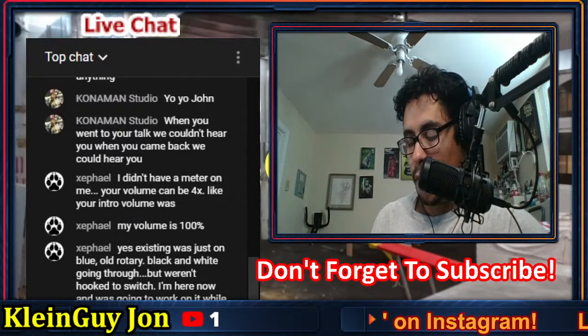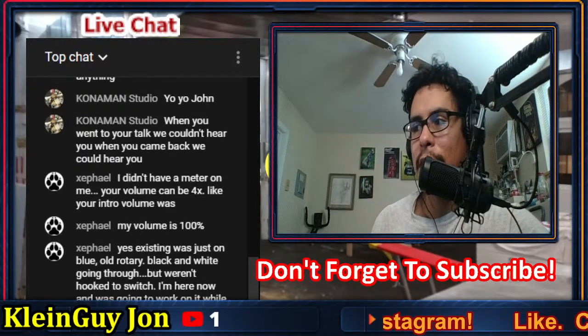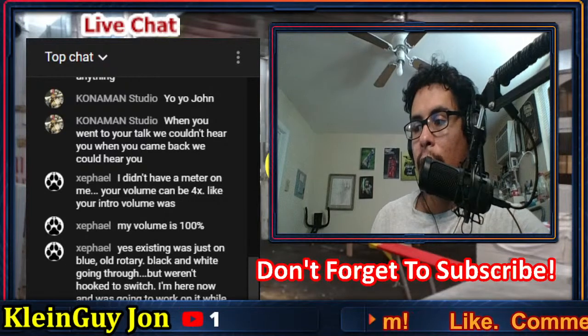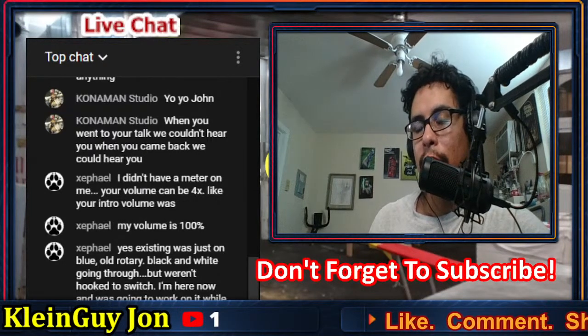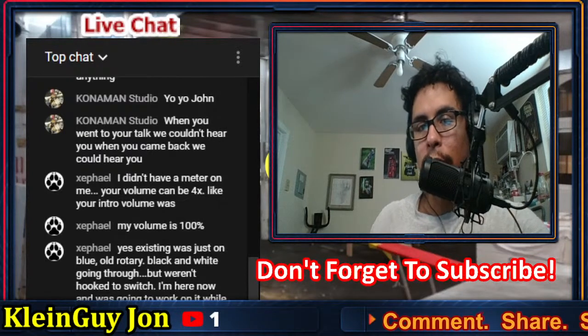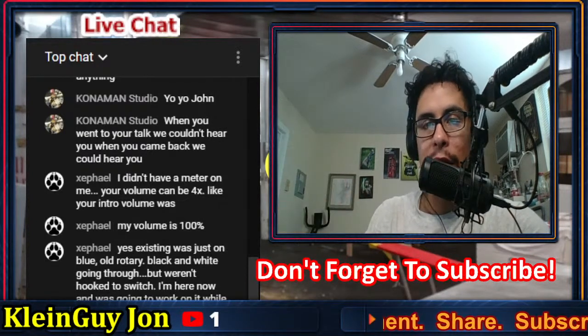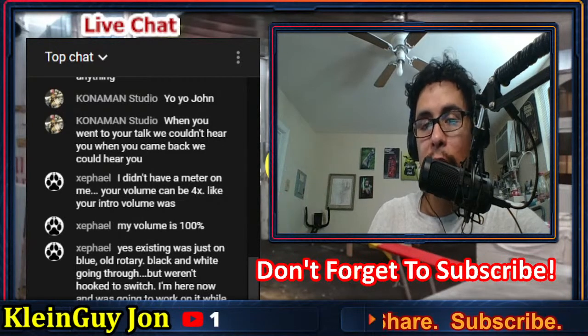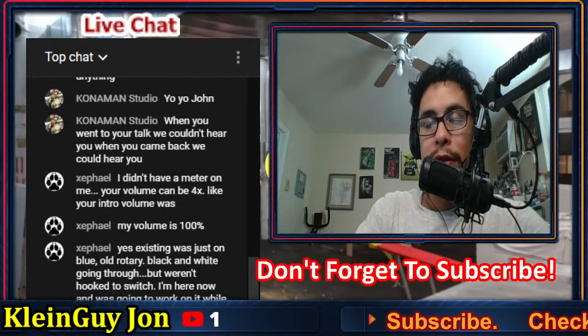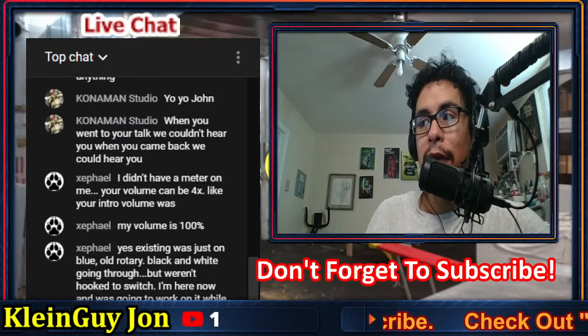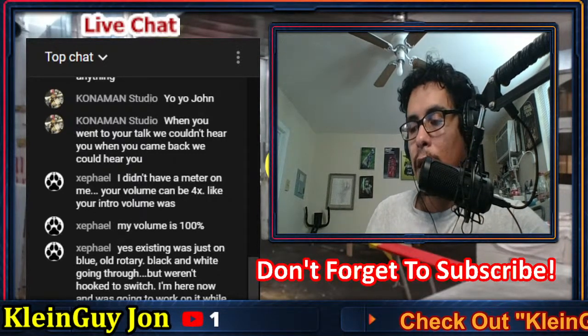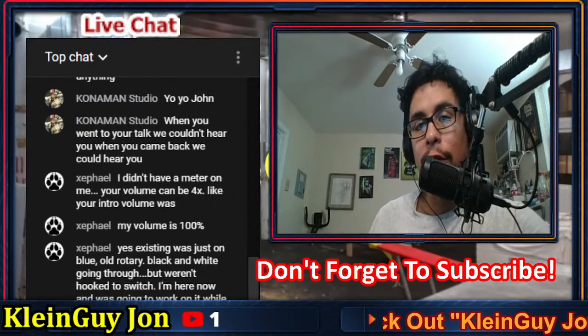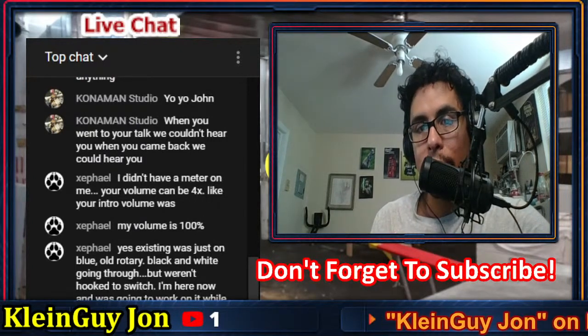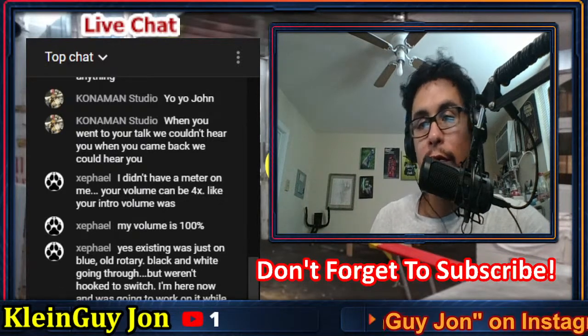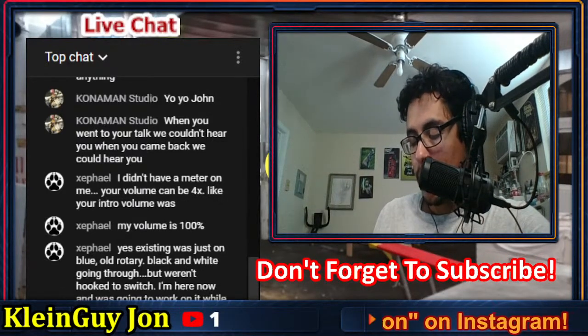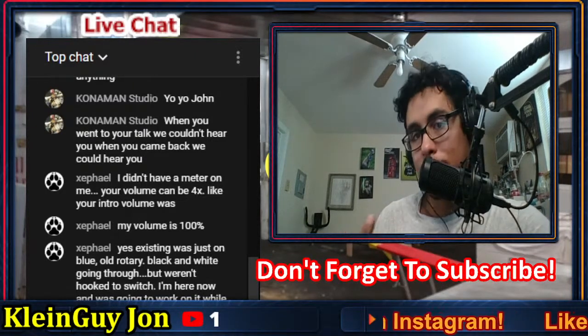So anyways, you might have to test continuity and see if your neutral wire is hitting. Take one of your probes to the neutral wire and your other test probe to the metallic box or something metallic, if you have a metallic box, or a ground wire, and test between there. If there's continuity, that could most likely be your neutral, your ground. Neutral is considered a ground, and your grounding conductor is your ground wire being bonded to the device or bonded to the box. Your ground is your neutral, and your ungrounded conductor is your hot, obviously.